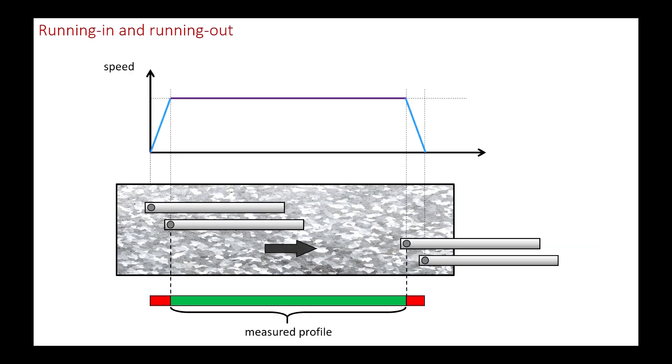Like any movement, the sensor cannot instantly reach its cruising speed. There is therefore an acceleration phase during which the displacement is not linear, so the spacing between the points is not regular. This is called the pre-travel, which is usually suppressed by the profilometer software. But it is nevertheless necessary to take this space into account on the sample, which can sometimes be a problem with small parts.